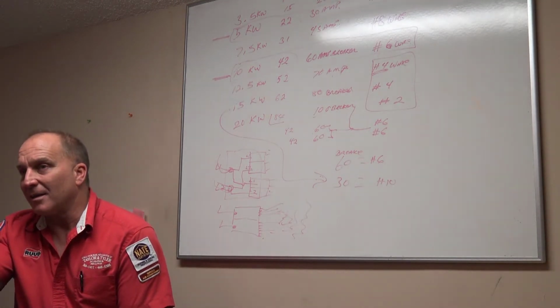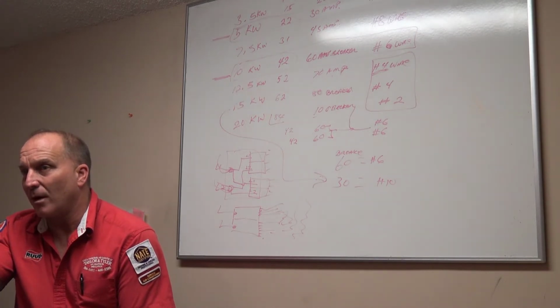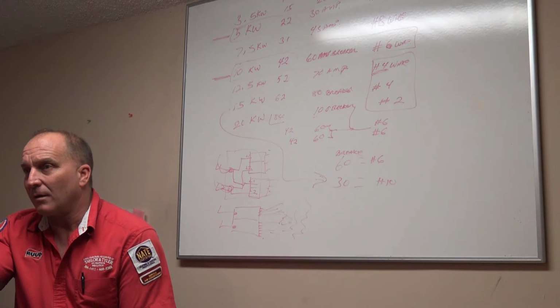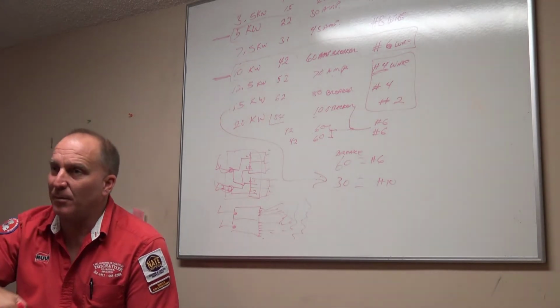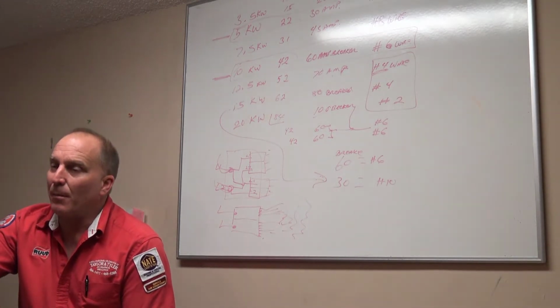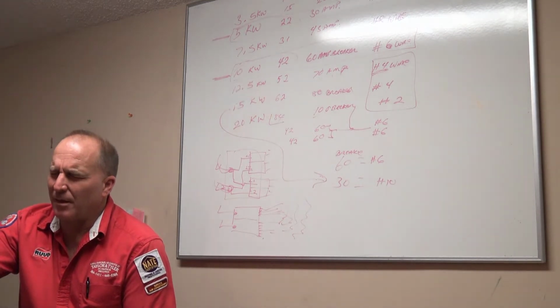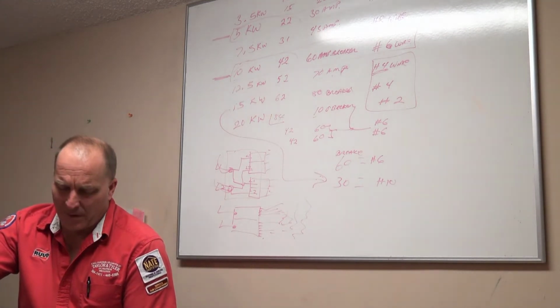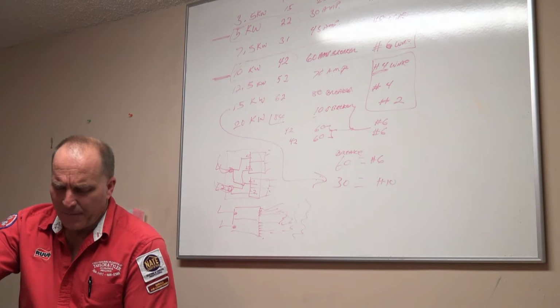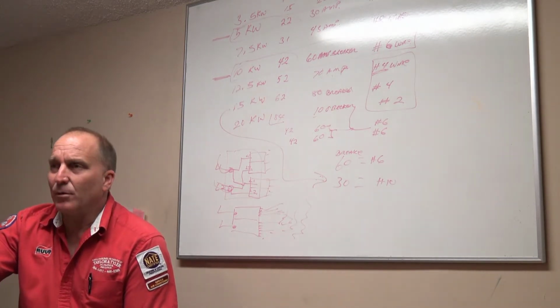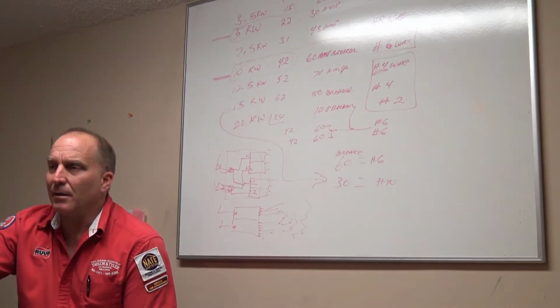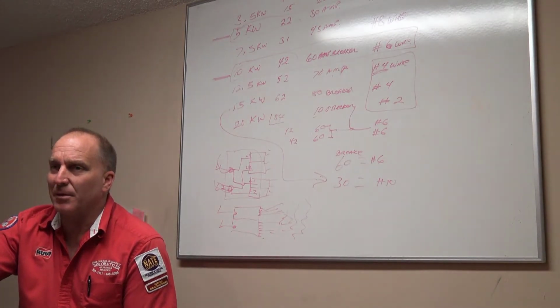A gas heating system, if you don't check your limit switches and your blower motor doesn't run, and your gas furnace is running, then you can have a whole bunch of heat up inside that chamber. So that's why you have multiple heat sequencers, limit switches up in a gas heat system. Here we have an electric heat system, so we have to test the limit switch. And how do we test the limit switch?